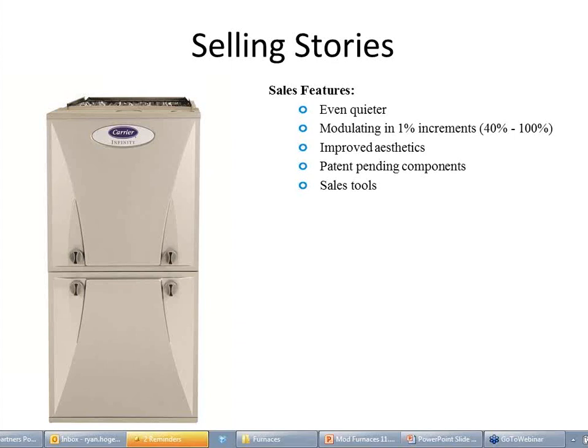The gas valve is fully modulating. It goes from 40 to 100% in 1% increments. So 40, 41, 42, etc. So it's basically, if you want to think of it this way, a 61-stage gas furnace, right? Whereas normally we'd have 1, 2, or 3 stages. This is 61 stages. So just right there, you can kind of see how much more controllable it's going to be and how much more comfort it could possibly provide.